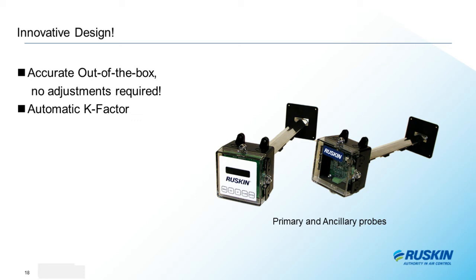This product is being configured prior to shipment to display CFM. Just take it out of the box and install. No adjustments are required for most installations. But what do you do when the installation really sucks? The TAB guy says, you can't measure the air there.